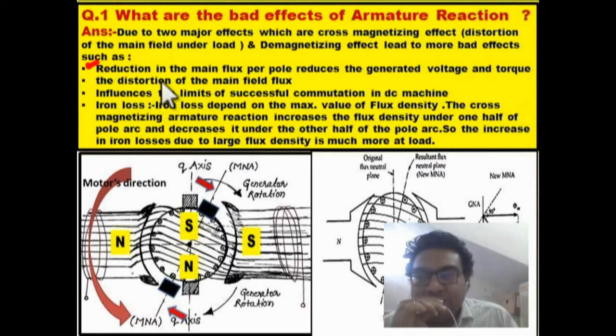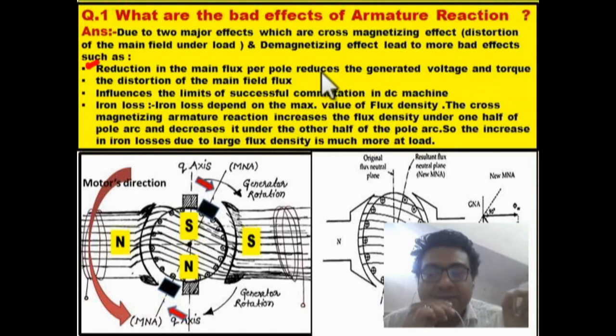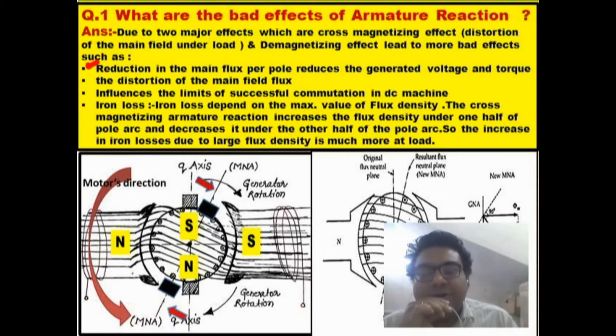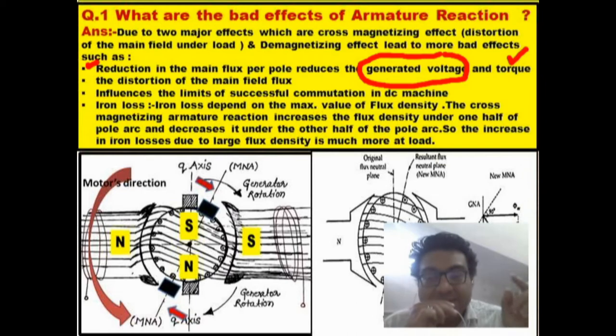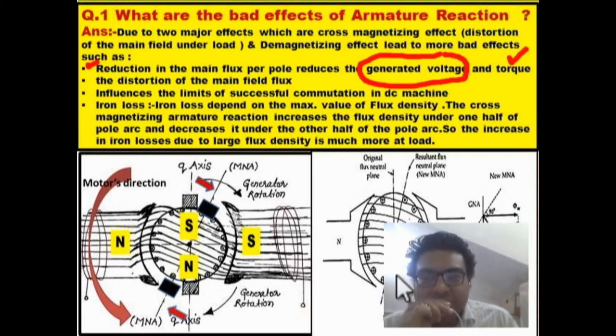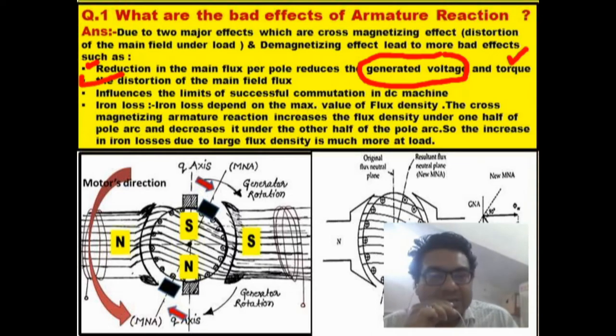Due to the distortion and reduction of main flux, what happens is: if this is a generator, then the generator voltage will decrease — there will be a reduction in generator voltage. And if it is behaving as a motor, then the motor's torque decreases, because torque is directly proportional to flux, and EMF is also directly proportional to flux. This is a very important point.